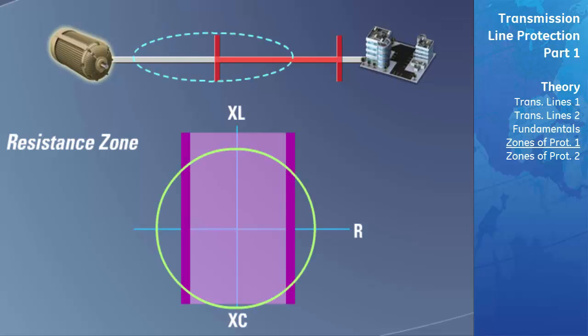For example, if an impedance zone detected the impedance of the line just slightly enter its zone of protection due to a fault occurring towards the end of its zone of protection, the resistive zone can be used to verify that the fault is actually on the transmission line because the impedance of the fault is mostly resistive. In this configuration, the resistance zone would be giving the impedance zone permission to trip.